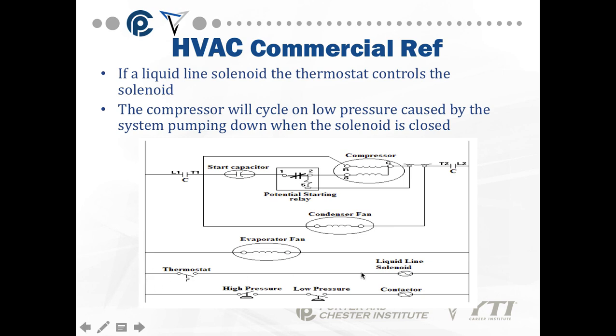In that case, the thermostat closes, energizes the solenoid coil, which opens a refrigeration line. Once the pressure comes up, it closes the contactor — this is for a pump-down system — then energizes the compressor and condenser fan. As with all commercial systems, the evaporator fan runs constantly.